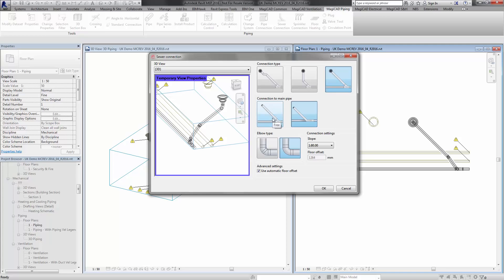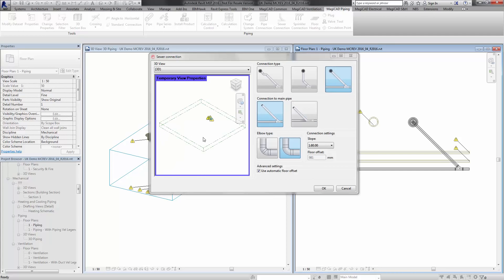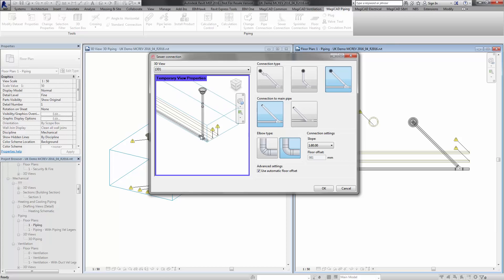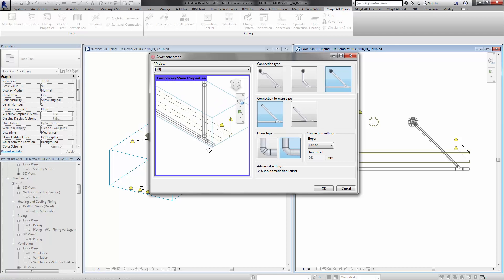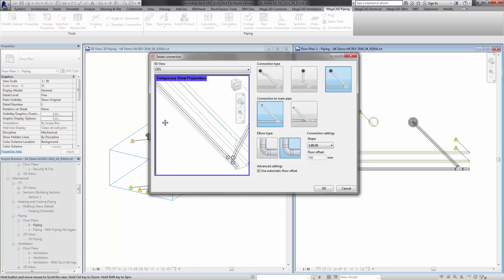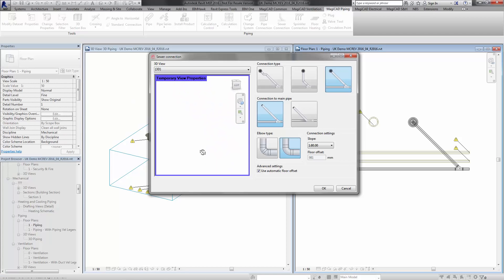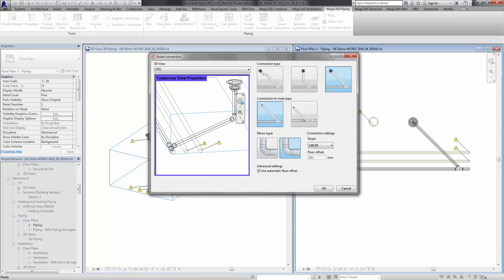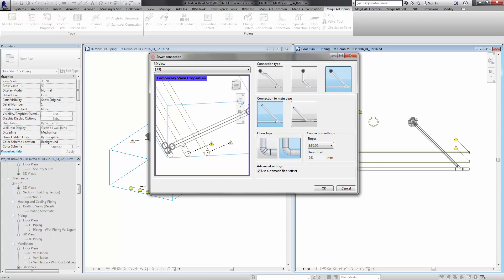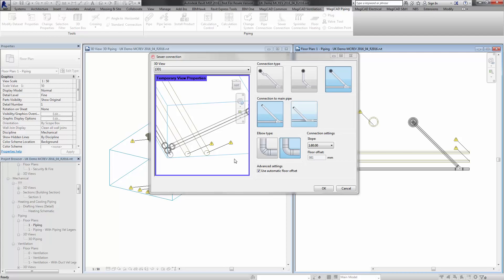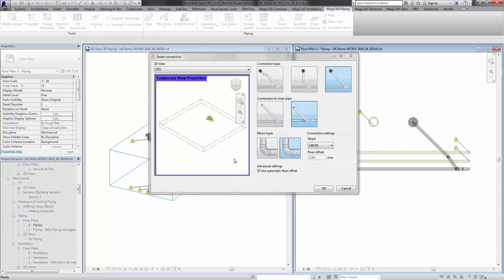For example, if I choose the free connection it will reconfigure, but this time you may have a clash with the other pipework because it drops off the bottom of this particular gully and then interferes or crashes into the other two pipes. If you click vertical, it will mitigate that clash and put the vertical connection on.